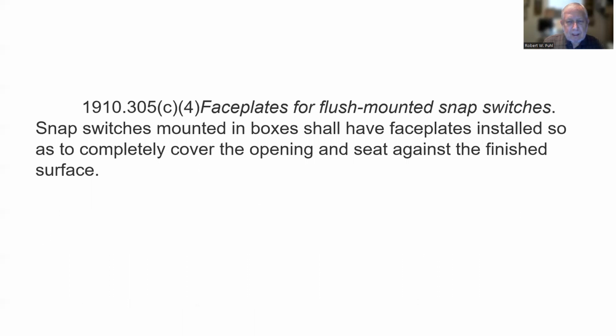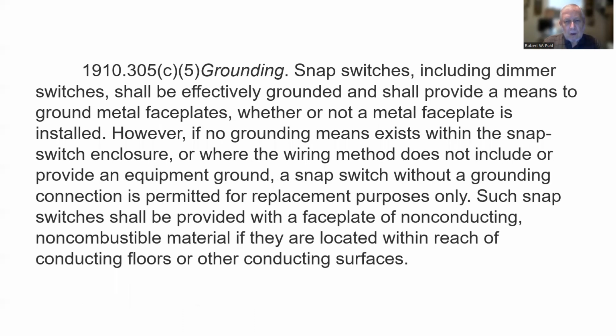Faceplates for flush-mounted snap switches. Snap switches mounted in boxes shall have faceplates installed so as to completely cover the opening and seat against the finished surface. Grounding. Snap switches, including dimmer switches, shall be effectively grounded and shall provide a means to ground metal faceplates, whether or not a metal faceplate is installed.